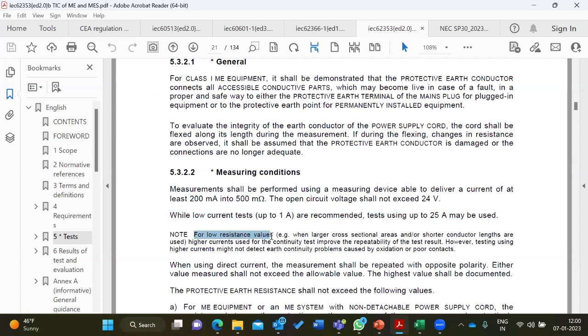Now note, for low resistance values, when a large cross-sectional area and shorter conductor length are used, higher currents used for continuity test improve the repeatability of the test result. However, testing using higher currents might not detect earth continuity problems caused by oxidation or poor contacts.